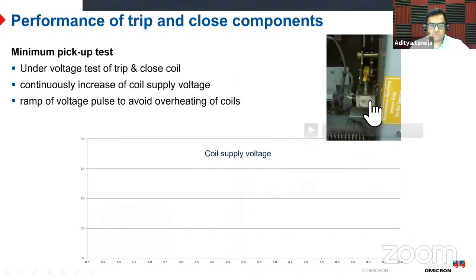So I'll just show you a video where there is a coil here, and it is trying to operate the mechanism. So there is some kind of a moving part, a plunger, which operates this latch, the yellow latch. And this latch, once it dislodges, operates the breaker. We want to find the minimum force required for operating this mechanical thing. So what we try to do is we give a low voltage, 25% of the rated, and try to operate. If it doesn't operate, let it cool down for a few seconds. Then try again with a higher voltage. We go like this till we are able to move it. So I'll just start the video. You will see this operating, and you will also see the voltage profile that we are using to operate this.